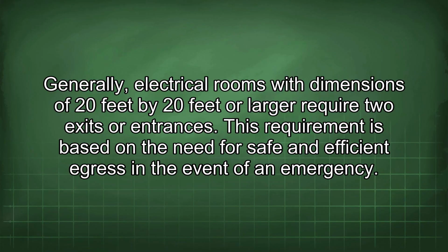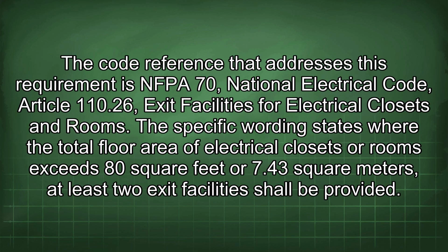Generally, electrical rooms with dimensions of 20 feet by 20 feet or larger require 2 exits or entrances. This requirement is based on the need for safe and efficient egress in the event of an emergency. The code reference that addresses this requirement is NFPA 70 National Electrical Code, Article 110.26, Exit Facilities for Electrical Closets and Rooms. The specific wording states where the total floor area of electrical closets or rooms exceeds 80 square feet or 7.43 square meters, at least 2 exit facilities shall be provided.